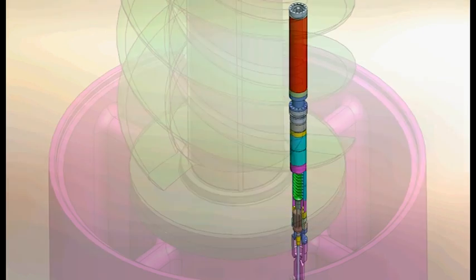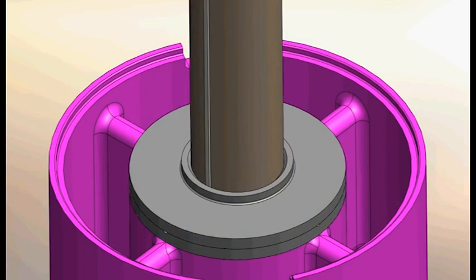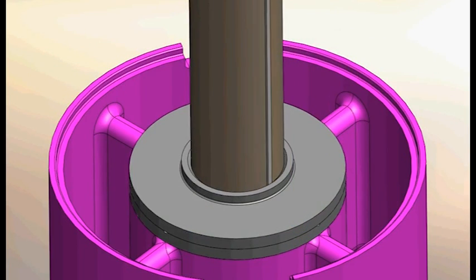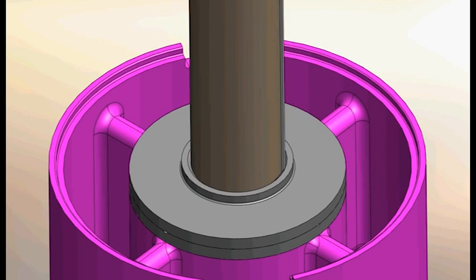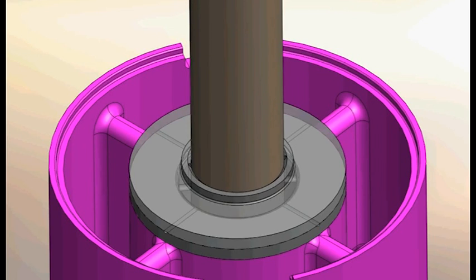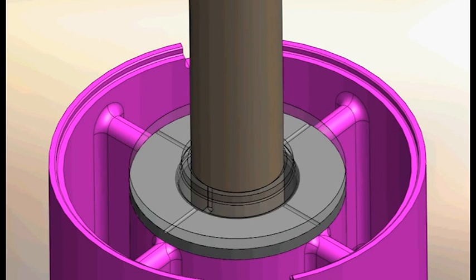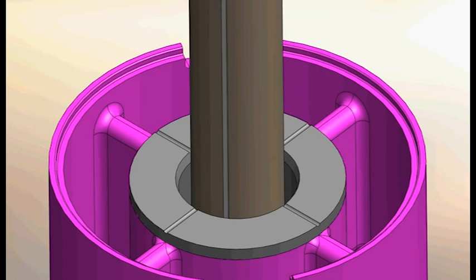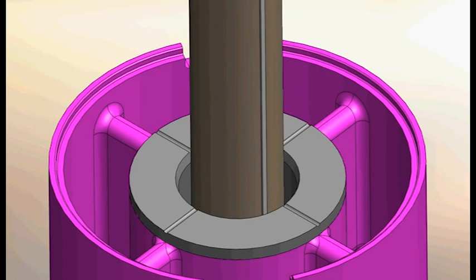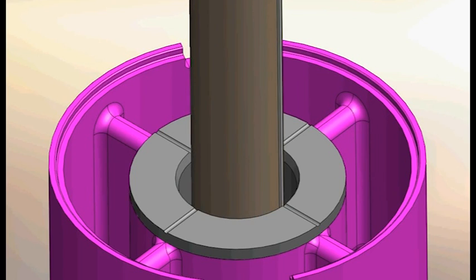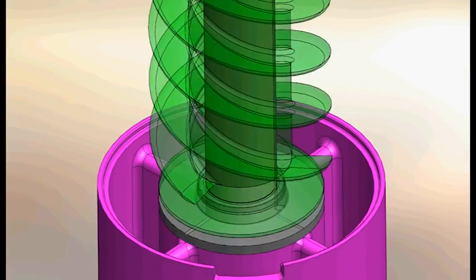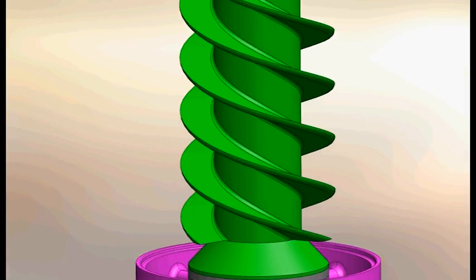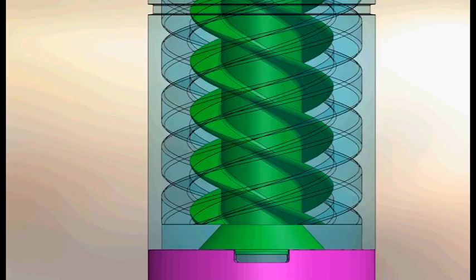Each rotor is supported on the top and bottom of the stage with radial and thrust bearings. As a result, the V-Pump does not suffer from up-thrust and down-thrust issues like a conventional ESP. With each rotor-thrust bearing carrying the thrust from its own rotor, very little thrust is transferred to the OEM seal section.